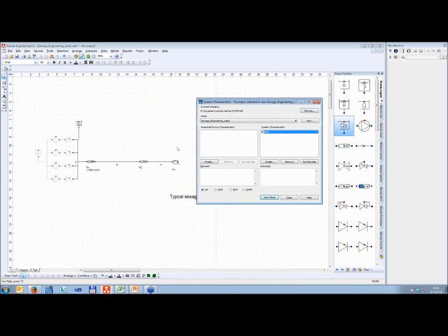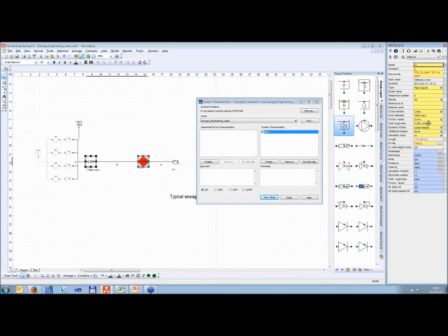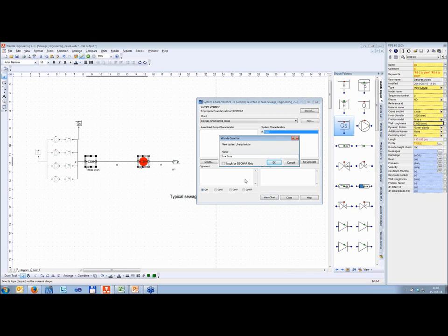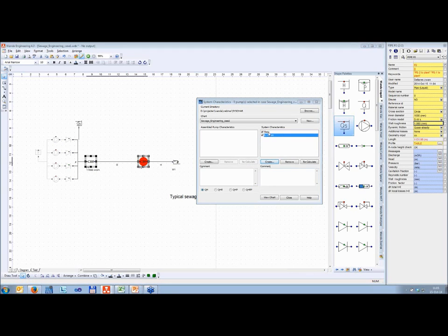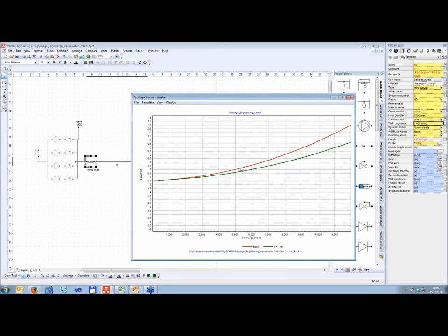Let's change a little bit — for example, the wall roughness in the system. It's now five millimeters, which is relatively high. Let's make it a little bit less and put it to one millimeter. We again do Create and call it 'K is one millimeter.' It does some calculations, and now you can see I have two system characteristics. If I click View Chart, I see them both.